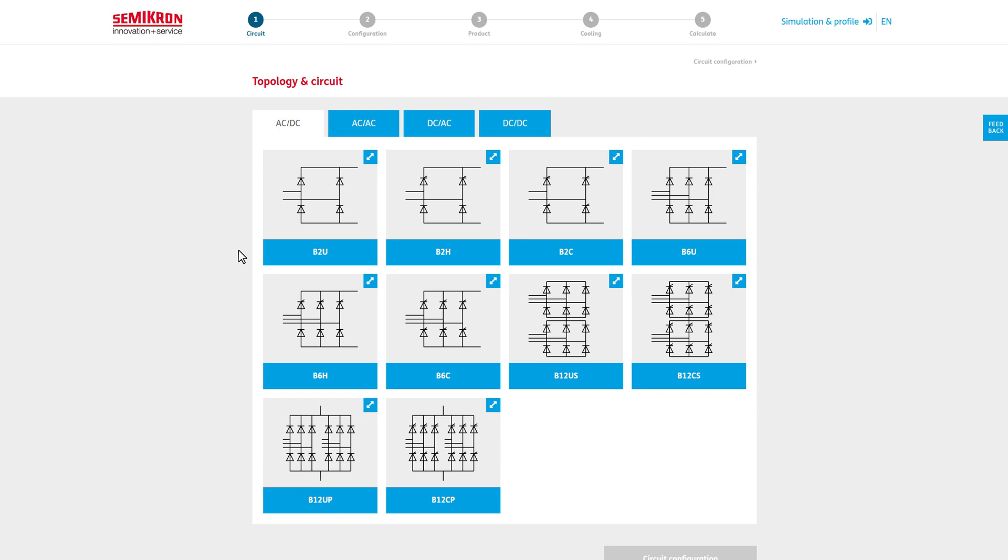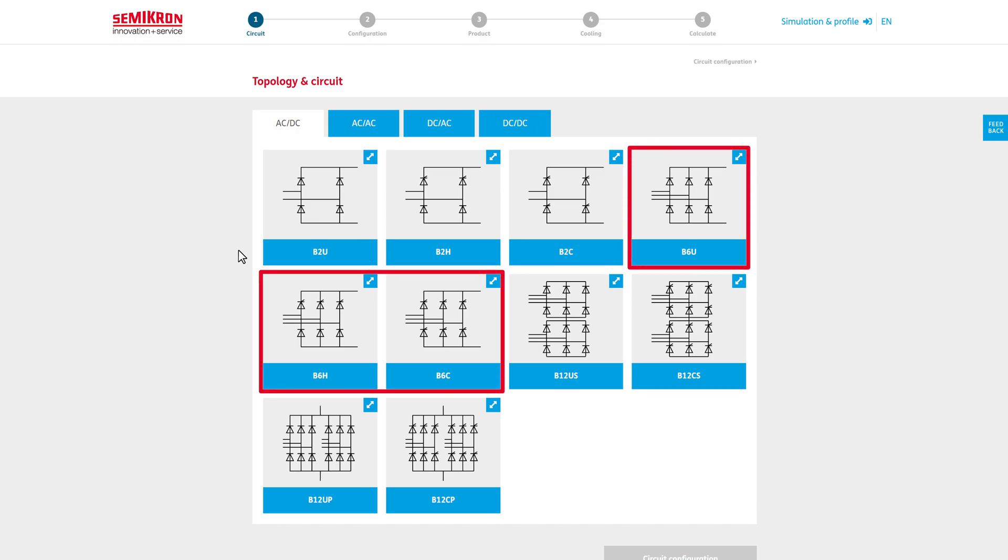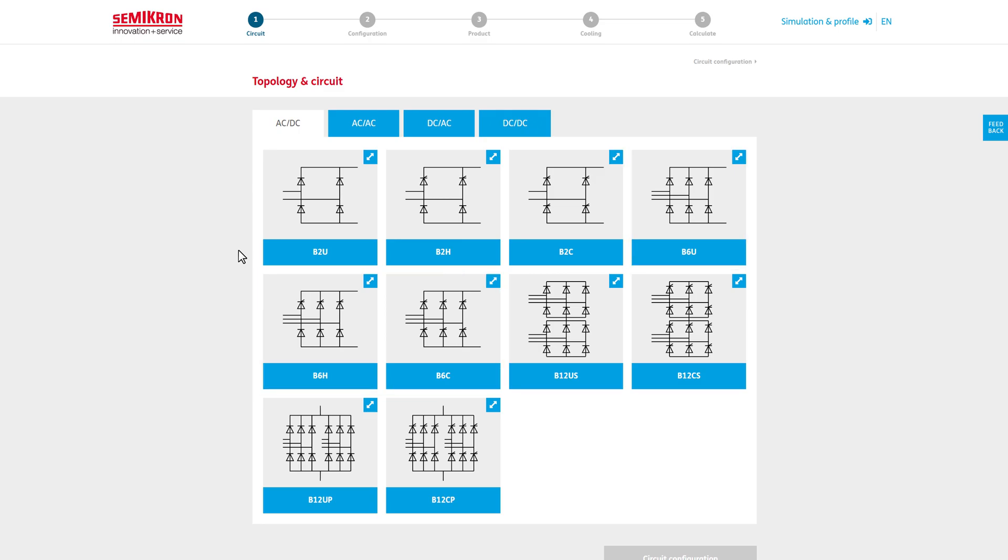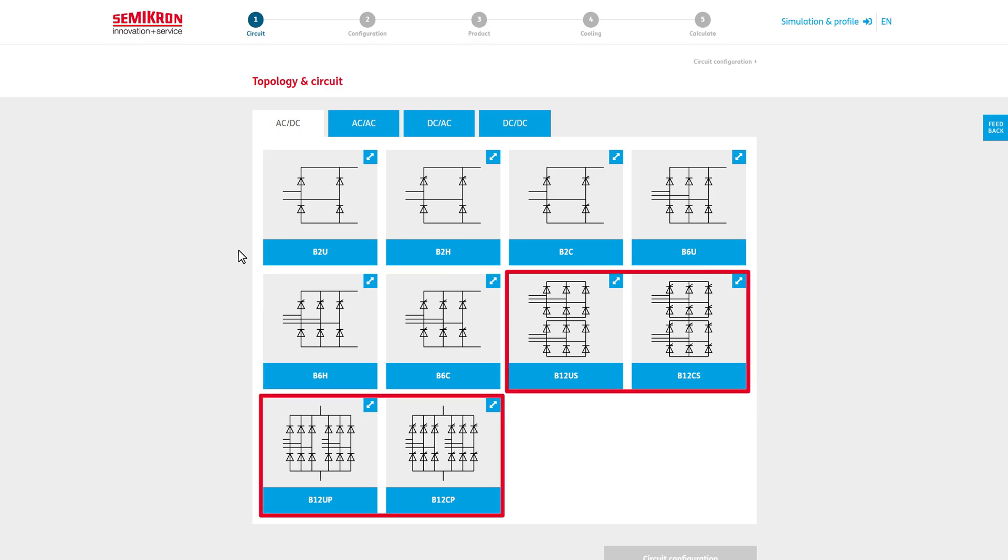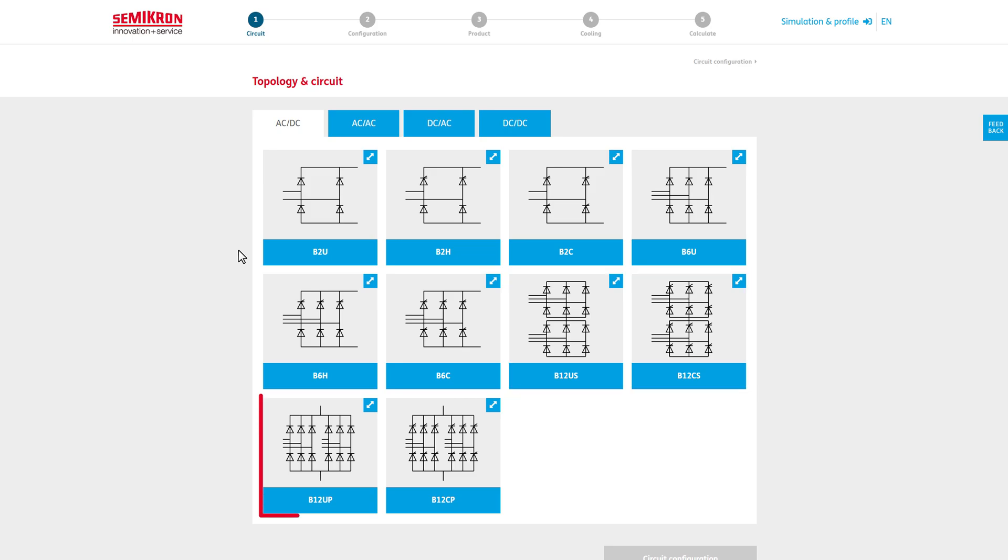There is a choice of single-phase rectifiers or B2, three-phase rectifiers B6, and so-called 12-pulse rectifiers B12, which may be considered in a series connection or a parallel connection of two three-phase rectifiers.